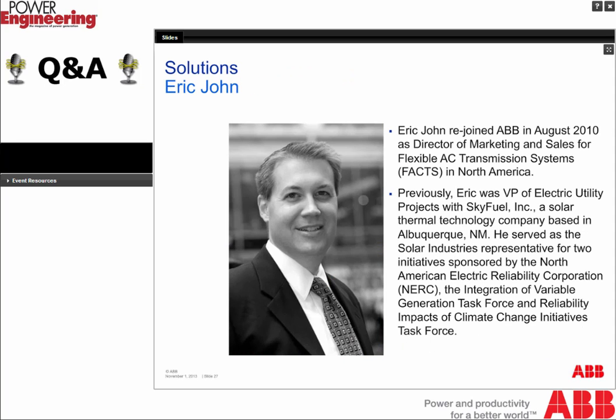It's kind of a broad question. I think the larger the unit that's being converted, the more complicated the conversion is going to be. As a generator gets up in rating to hundreds of megawatts, you have to contend with hydrogen cooling and more complicated lube oil systems. Depending on the age of the generator, you will most definitely have to make modifications to the excitation system and probably the controls on the generator. The extent of those modifications will depend on the age of that equipment and whether it has been upgraded or modified in the past. So in general, the larger the unit, the more extensive the modifications and changes to operate it will be.